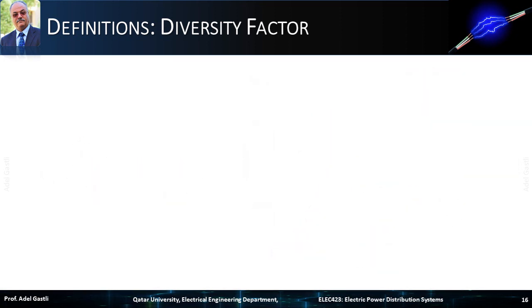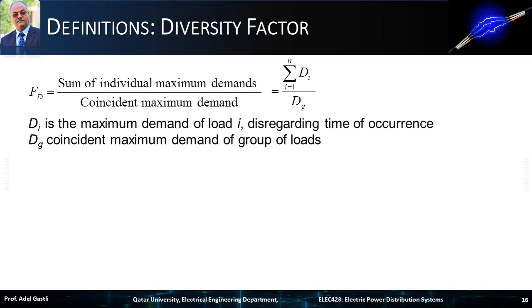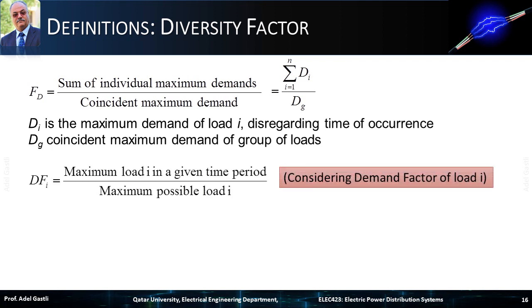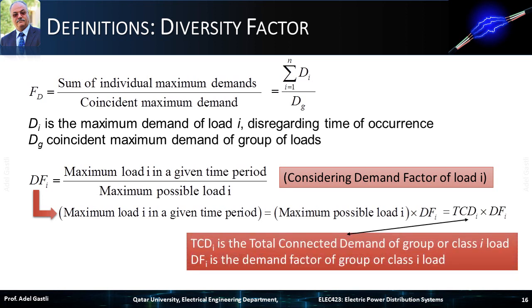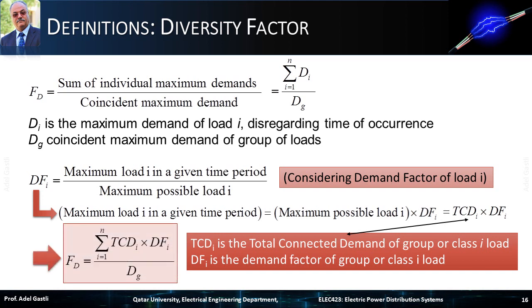In summary, the diversity factor is calculated as the ratio of the sum of individual maximum demands to the coincident maximum demand, where DI is the maximum demand of load I disregarding time of occurrence, and DG is the coincident maximum demand of the group of loads. The demand factor of any load I is the ratio of the maximum load I in a given time period to the maximum possible load I. This leads to expressing the maximum load I as the total connected demand TCDI times the demand factor DFI, allowing the diversity factor to be expressed as a function of the demand factor.